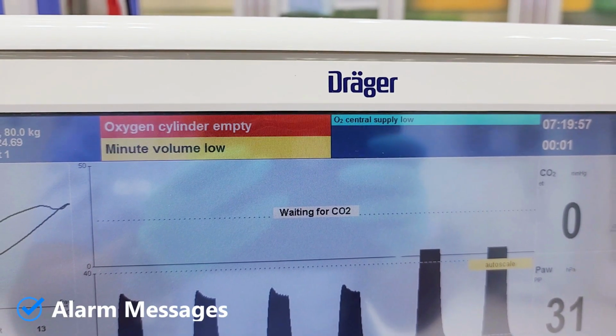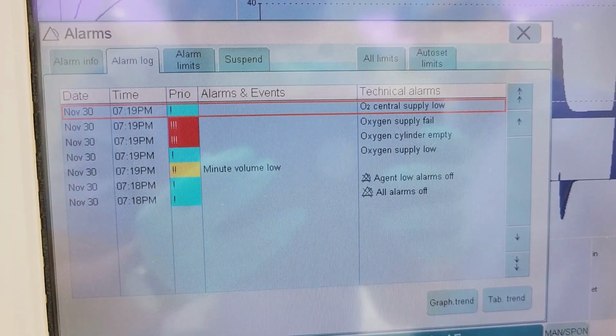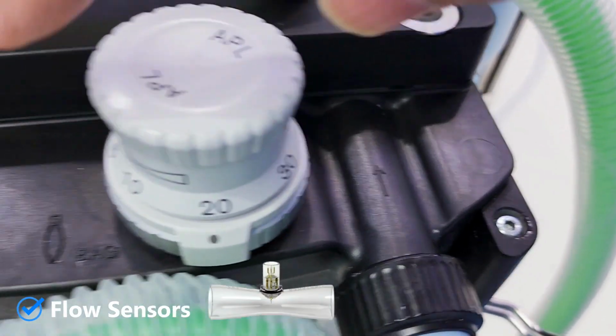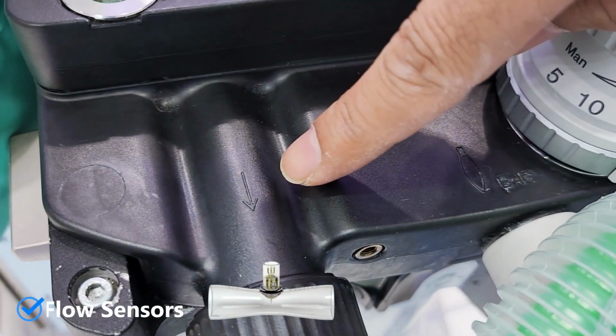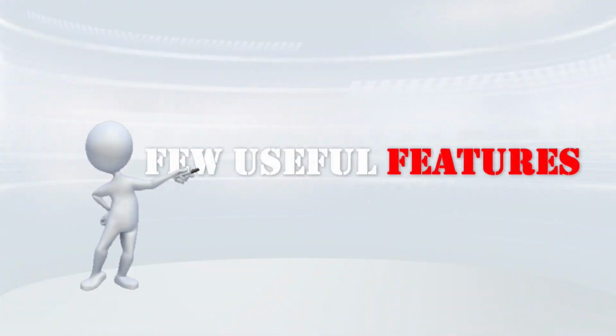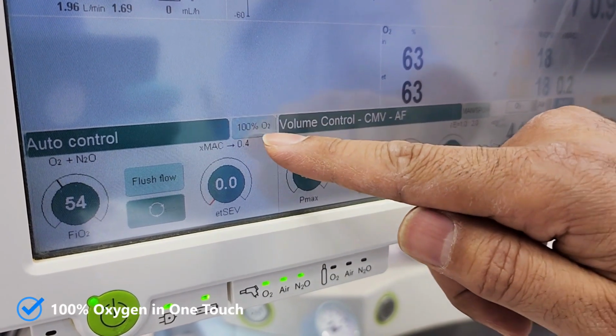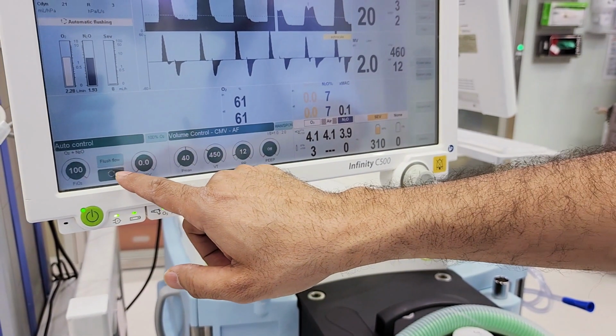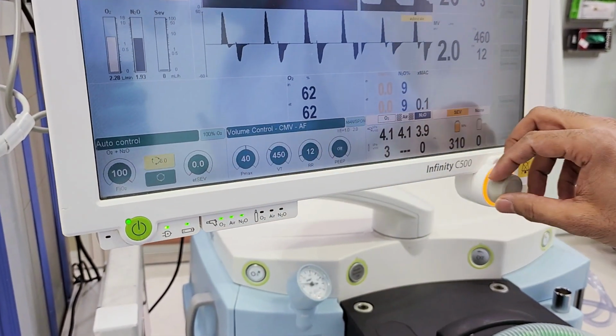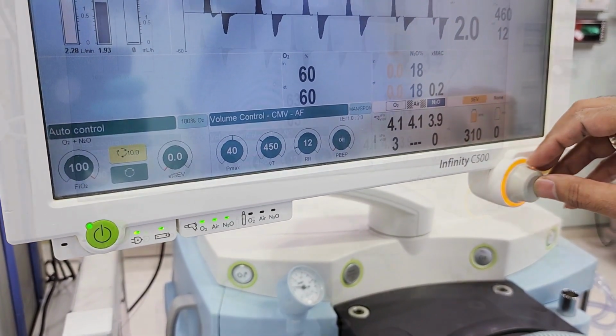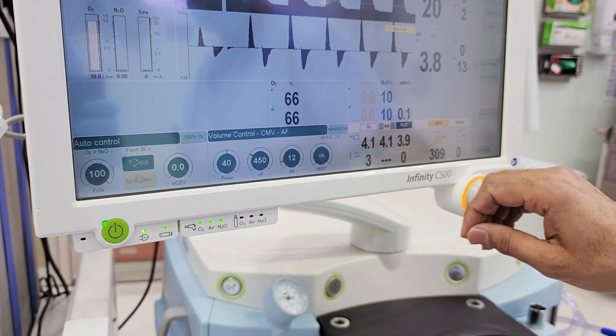Alarm messages are color-coded: red, yellow, and blue. The color is according to importance levels. Messages with the highest importance are in red color. There are 2 flow sensors inside the breathing system, one for inspiration and one for expiration. Set 100% oxygen in one touch. Increase the fresh gas flow during auto control mode. Use the flush flow button to increase flow for 60 seconds, and use minimal fresh gas flow to go back to auto control mode.